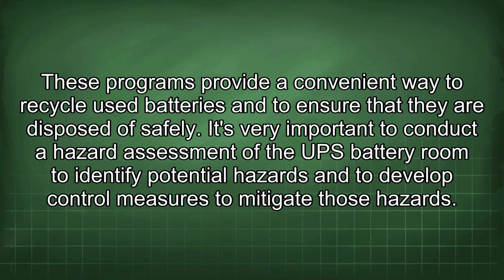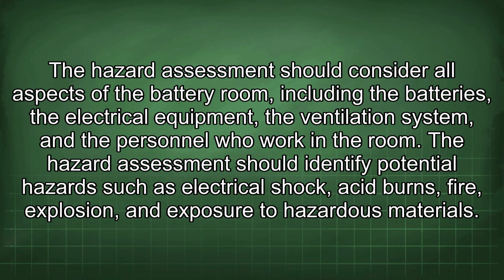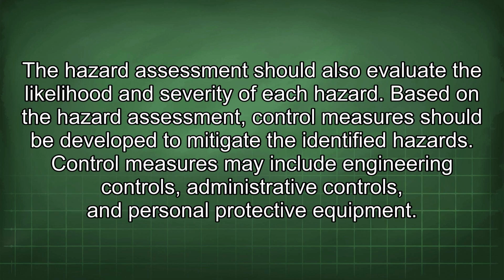It's very important to conduct a hazard assessment of the UPS battery room to identify potential hazards and to develop control measures to mitigate those hazards. The hazard assessment should consider all aspects of the battery room, including the batteries, the electrical equipment, the ventilation system, and the personnel who work in the room. The hazard assessment should identify potential hazards such as electrical shock, acid burns, fire, explosion, and exposure to hazardous materials. The hazard assessment should also evaluate the likelihood and severity of each hazard.